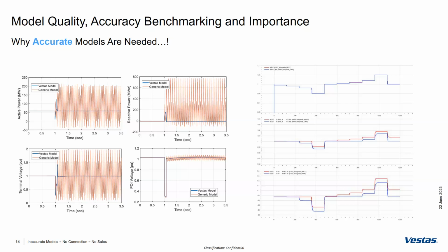So this has a positive impact on the utility, the developer, and also Vestas, because it lets the project move forward with a better business case. That's some of the challenges with generic models today, as Jonathan also alluded to. On the right side, it's not really a severe case. In the top plot, a voltage reference is fed to a generic model tuned to best match the user-defined model with the exact same parameterization. Over time, the response actually deviates. That's because there are a lot of differences in these models, and this is just a simple voltage reference change. We hear a lot in the industry that generic models are inaccurate around fault ride-through, small nuances, but here it's a voltage step change, and we're talking 5 to 10% difference in the reactive power response.